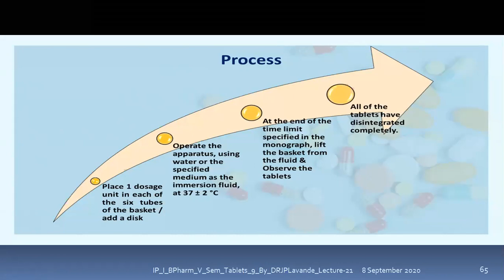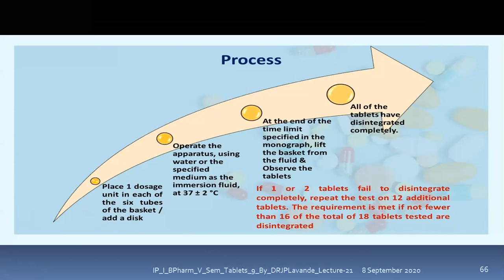We cannot say that it fails, but we need to repeat the test by taking an additional 12 tablets. The requirement is met if not fewer than 16 of the total 18 tablets tested are disintegrated. Now with these 12 additional tablets, that means 12 plus the previous 6, the total will be 18 tablets. Now out of 18 tablets, if 16 tablets get completely disintegrated, then we can say that the tablet passes the test for disintegration.